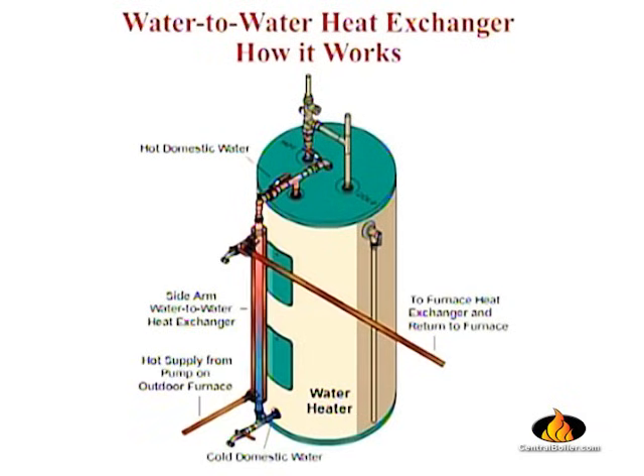So that leads us, Mark, to this: how does it actually heat a domestic water system? Well, that's a real nice benefit of the outdoor furnace, that you can heat 100% of your domestic water. When I say domestic water, I mean the water you use for washing dishes, washing clothes, and showering. The way we do that is we put a water-to-water heat exchanger, also known as a sidearm exchanger, on the water heater itself. So the two waters, our outdoor furnace water and your domestic water, run side by side in the heat exchanger. They never mix, they never touch, they just run side by side in a tube, and we transfer that energy, that heat, into your domestic water.